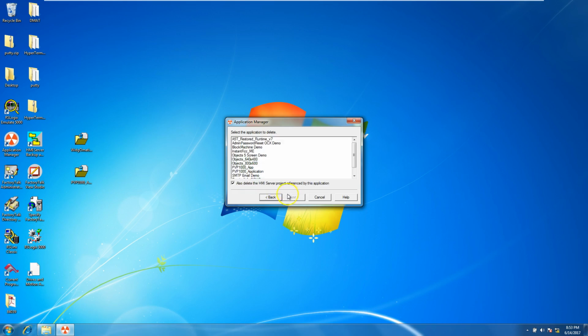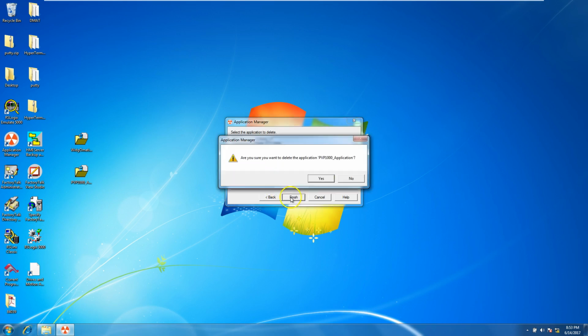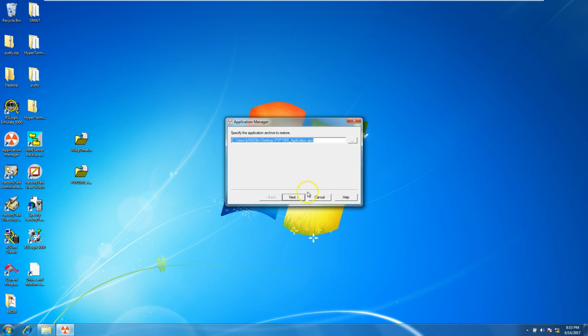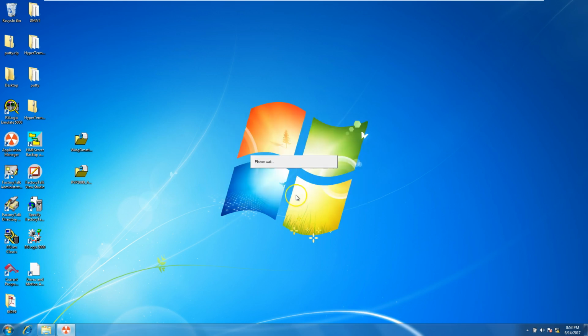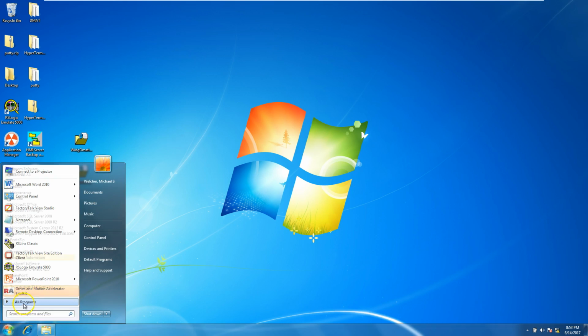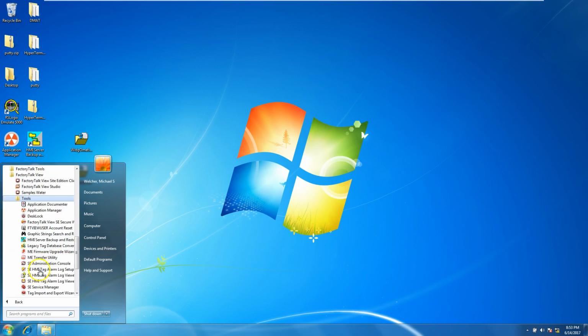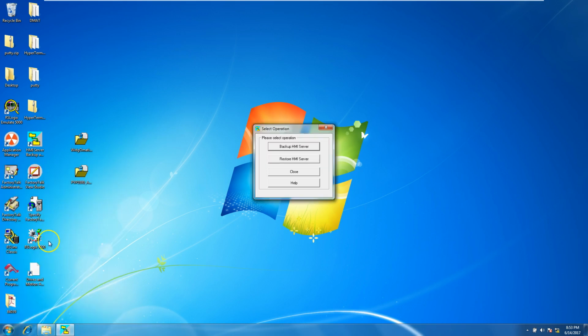So let's delete this file. Okay, so now let's convert it back over to an HMI project with the proper name. It could be the file name, because FactoryTalk Studio ME is sometimes specific about names. If I had to guess, that would probably be what it is.